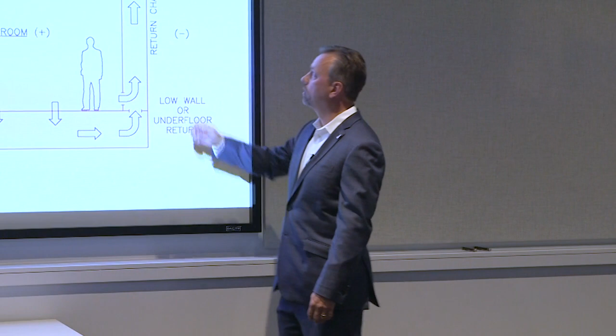In a nutshell, this is a very generic representation of what a clean room is. It's a space that's generally positively pressurized compared to surrounding areas, though it can be negative, and we'll get into that a bit. Air is pushed through the ceiling through HEPA filtration, then returned through a raised floor if you have one available, or through low sidewalls, back up and around again. That's how you deal with particulate control. You also have makeup air pushed into the space, to pressurize it and to compensate for exhaust pulled out of the room. That takes a lot of energy because you're preconditioning the air.